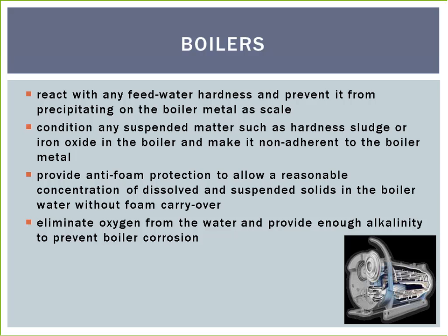2. Condition any suspended matter such as hardness sludge or iron oxide in the boiler and make it non-adherent to the boiler metal. 3. Provide anti-foam protection to allow a reasonable concentration of dissolved and suspended solids in the boiler water without foam carryover. And finally, 4.